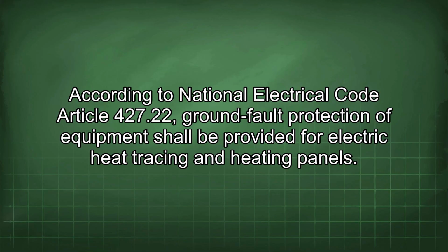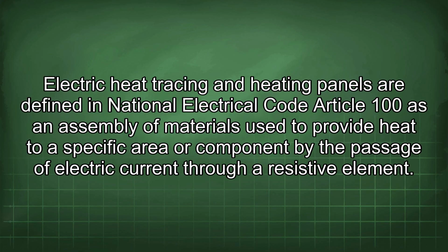According to National Electrical Code Article 427.22, ground fault protection of equipment shall be provided for electric heat tracing and heating panels. Electric heat tracing and heating panels are defined in National Electrical Code Article 100 as an assembly of materials used to provide heat to a specific area or component by the passage of electric current through a resistive element.